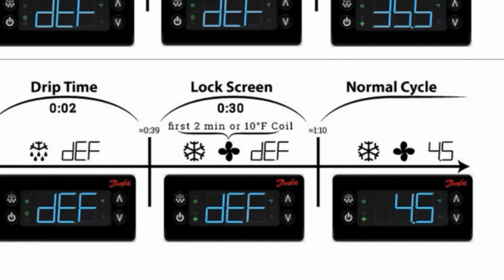And the reason we do that is really just to avoid nuisance calls from a customer saying their unit's up in temp, especially after a defrost cycle, on the freezer especially too, because we're going to have a heater that's going to bring the temperature in that space up a bit. So we have it read that DEF for 30 minutes.